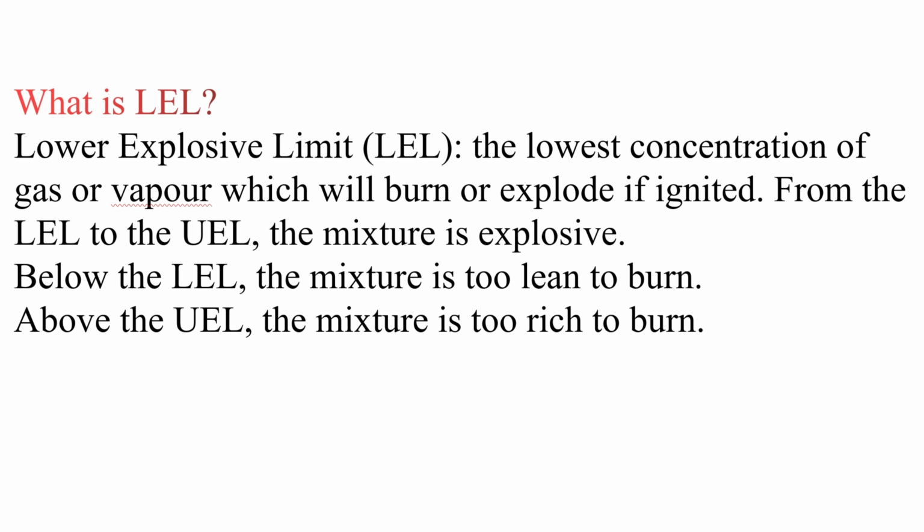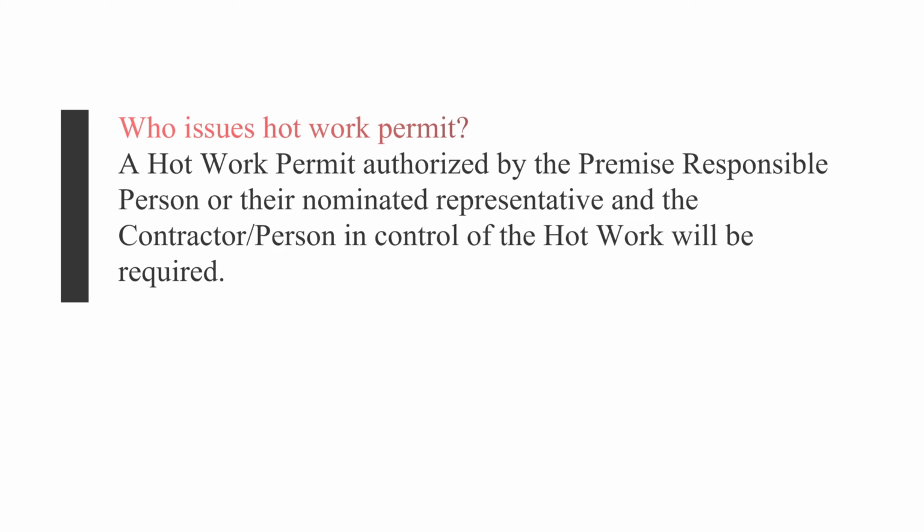What is LEL? Lower explosive limit. LEL is the lowest concentration of gas or vapor which will burn or explode if ignited. From the LEL to the UEL, the mixture is explosive. Below the LEL, the mixture is too lean to burn. Above the UEL, the mixture is too rich to burn.